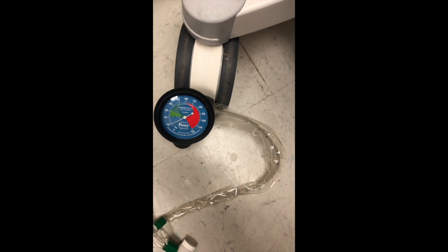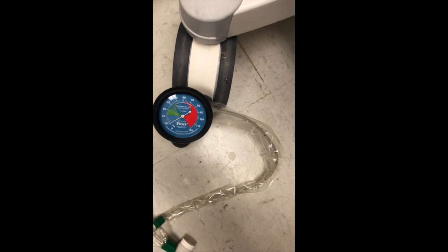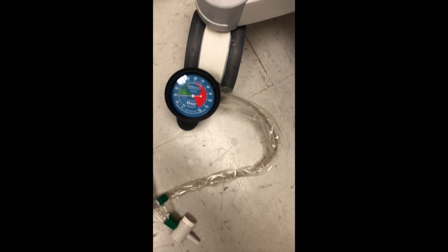cuff pressure. The reason to use this gauge is that it is very convenient, and it goes from 10 to 120 centimeters of water, which is helpful to measure the pressure. But you can use any gauge in here, including a mercury gauge, which I have done with the other lung, so that if you're short on these gauges or they cannot be found, we can just use a mercury gauge.